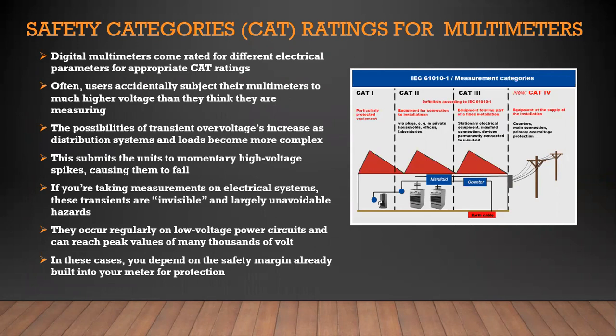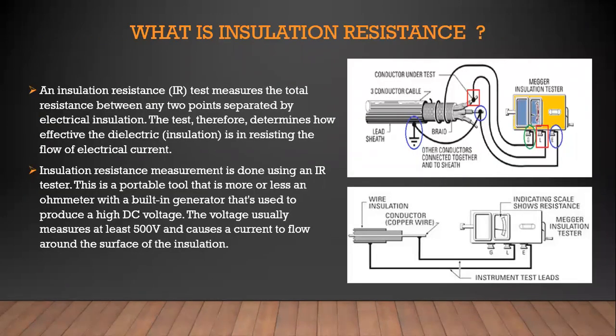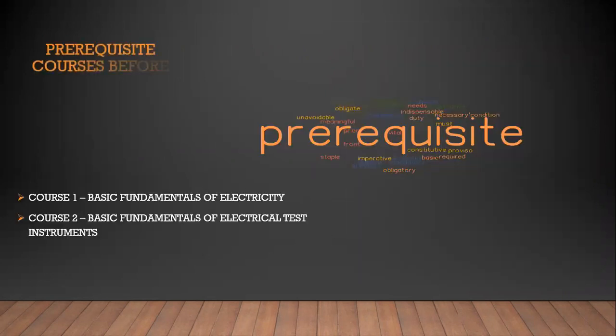your application. We always buy the cheapest ones, and they're not always the correct ones, the legally acceptable ones. So yeah, I explained the category specifications for measurement instruments. I go to insulation resistance testing. I explained to you how to test the geyser element if it's really faulty, if it's got a leakage on it, how to use the insulation resistance tester, and to determine if the element is actually faulty or there could be a circuit fault towards the appliance.